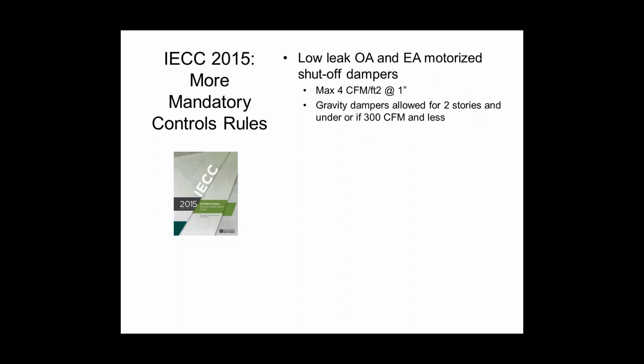So if you're buying a rooftop, for example, you already have an economizer, so you already have a motorized damper. You're probably fine if you order the low-leak damper and economizer controller; you're there. If you have a built-up system, then you're going to have to pay more attention to this.